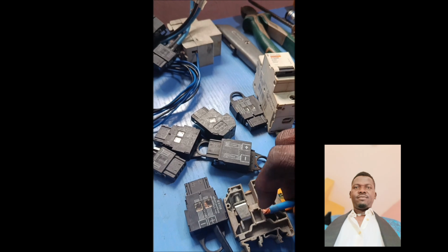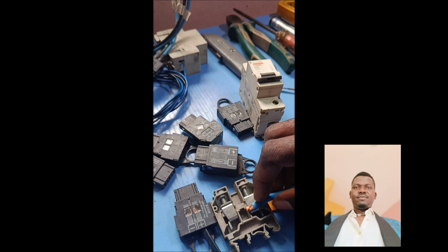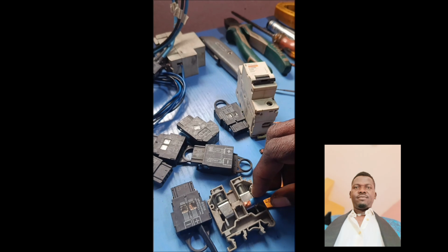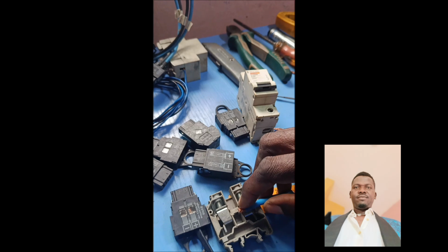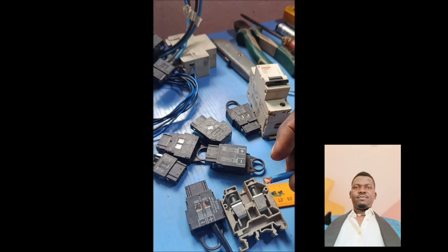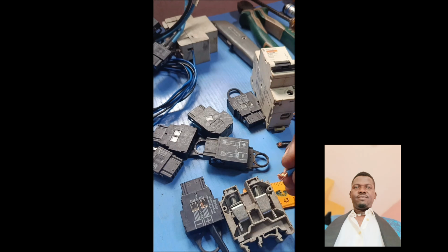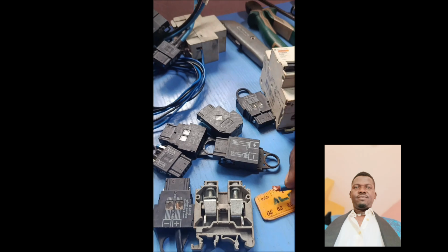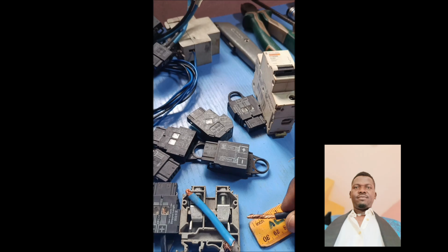Just because this stripped wire will be touching the body of this metal part, it will work at first, and it will be giving you current. But as time goes on, once there is a constant load on it, this point will start heating up, and from heating up, it will get burnt. So this stripping doesn't work for this. It might work for other connectors that need a short stripped length. This is it.